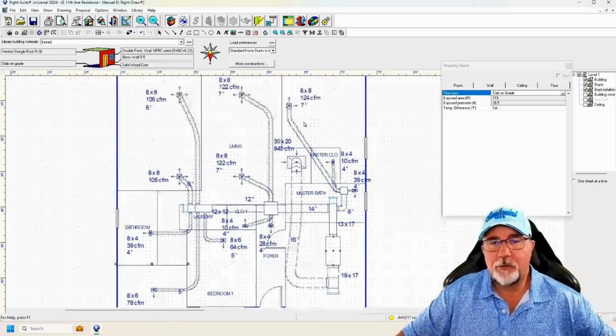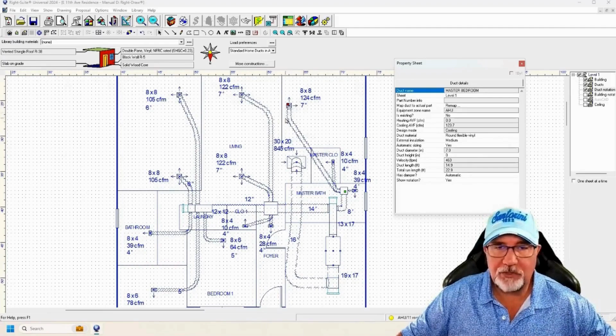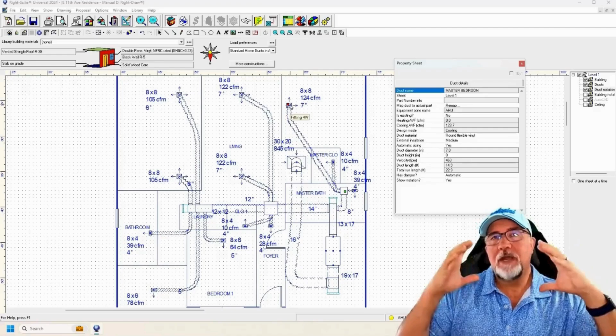Now, using this software, which has a Manual D process in it, it tells us what the size of that duct should be. And what it does is more than just the rulers. It looks at a lot of different factors. It looks at the velocity of the air, how long the duct is. Each of these transitions, like when this transitions into a grill, creates a restriction. So all these little things come into play to say, wait a minute, maybe a 7-inch duct is too big because the run is only 4 foot long. It'll put too much air through that 7-inch duct because it's only a short distance. There's very little restriction as the air comes off and branches into that, with no bends and loops and whatnot.